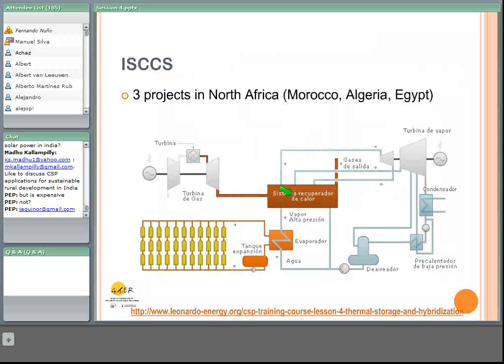With this type of configuration, the solar field size is limited, and the solar fraction, that is the amount of electricity generated from solar energy divided by the total electricity generated by the plant, is rather low, in the range of 10 to 15%, maybe 20% at most. Otherwise the relative size of the steam turbine and the gas turbine would have to be modified, and the operation in absence of solar energy would be less efficient. So there are limits for an efficient operation of these types of plants for the solar contribution.